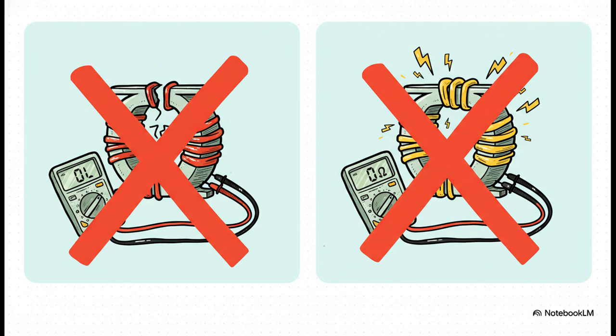Well, if your multimeter screen shows OL, that just means open loop. Think of it like a broken bridge. The wire inside that coil has literally snapped. There's no connection. That transformer is toast. On the flip side, if it reads 0 ohms or something super close, that means the coil has shorted out on itself. It's basically just a useless piece of wire now. In either case, that transformer has definitely failed.